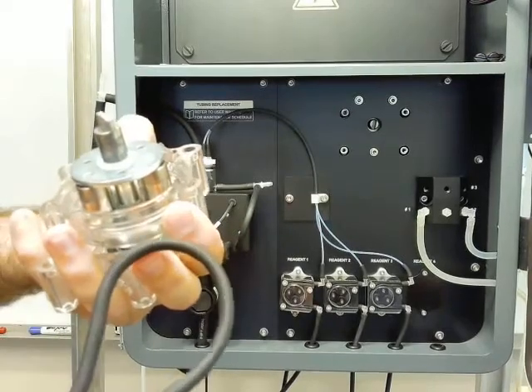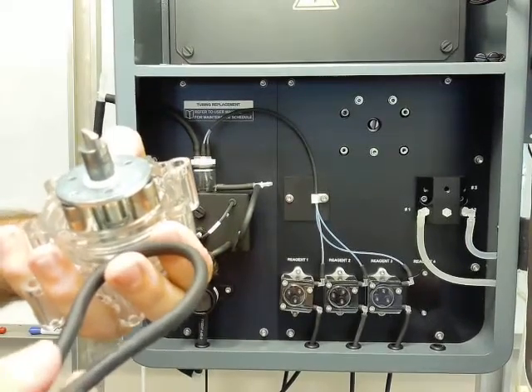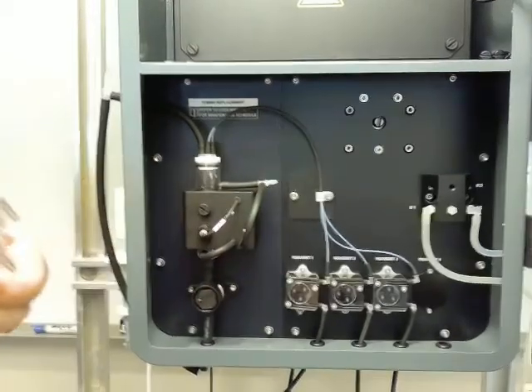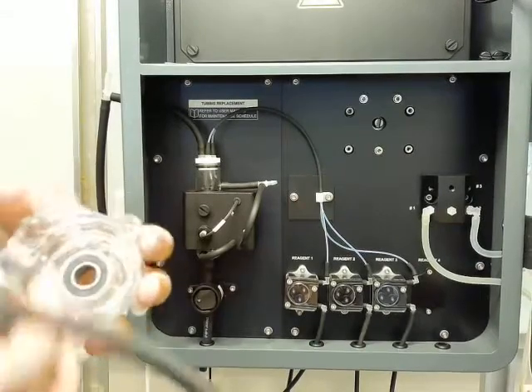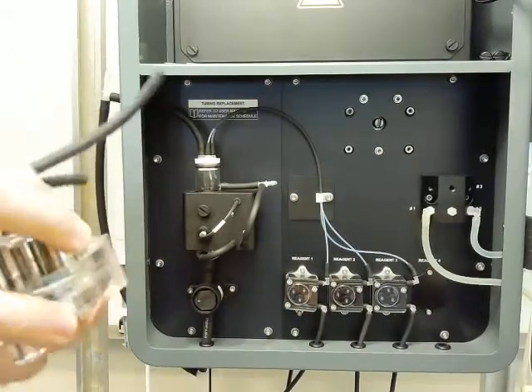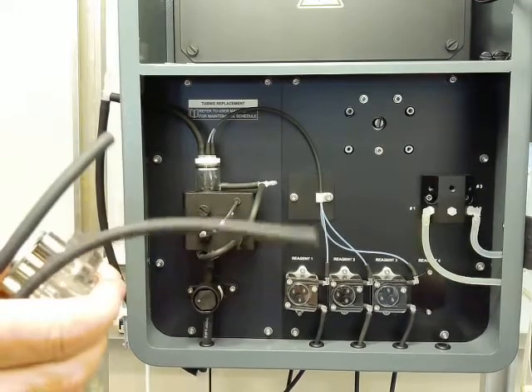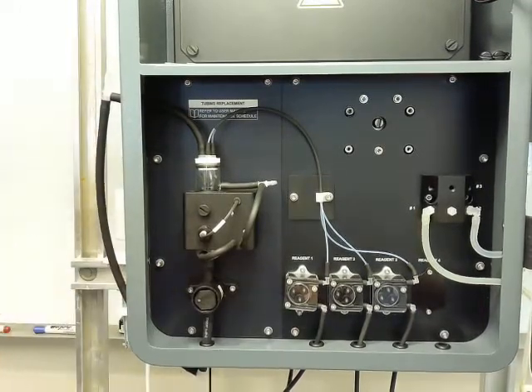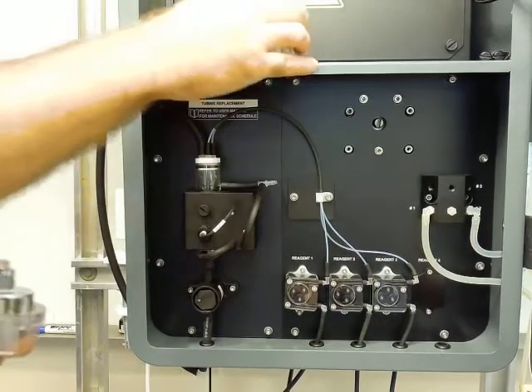What you might see after the quarterly stuff is a little bit more wear. Some of the tubing starting to break off and form debris on the inside of this pump head, and you just wipe it clean. Again, obviously, if you see any kind of leakage or tubing breaking all the way through, you'd want to say, hey, maybe we have to do this replacement a little bit more frequently so we don't end up in that situation.